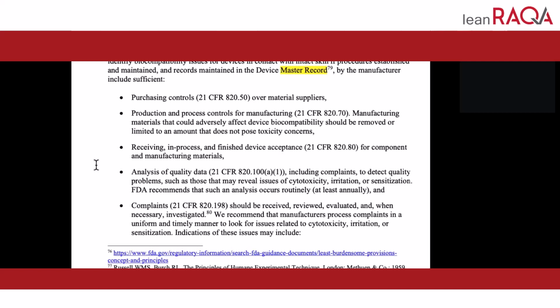Yeah, so that was a little bit disturbing to hear that they're not even trained in the QSR. But essentially, when they say device master record, yes, in a device master record you would put your material specs there. You would put your process specs for how you manufacture it. So if you were picking something like silicone, you would say what temperature, what pressure, what fixture you were going to mold the silicone in or extrude the silicone in. If you had final inspection, in process, incoming, you would say what those procedures are.